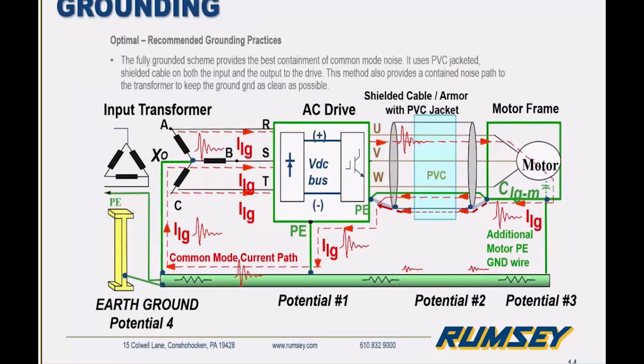So not only is it important to make sure we have a properly grounded transformer and we understand what type of ground system is being used, we want to follow the proper grounding schemes throughout the rest of the system. So what this diagram is showing is that the motor ground, the drive ground, and the transformer ground are all connected at some point. And this does a good job of containing the common mode noise that is created by the drive, and gives us a clean ground grid.